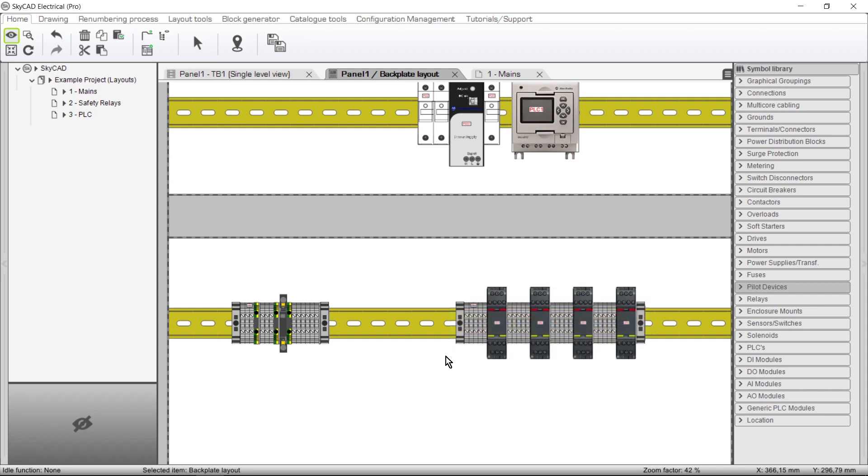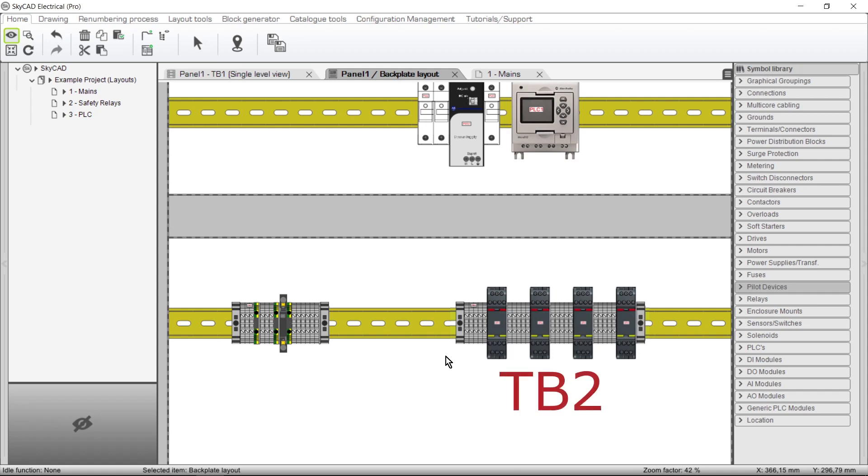which consists of some terminals, a safety relay, some more terminals, and so on. Conventionally, to achieve this layout, each set of terminals would have to belong to its own Terminal Strip, which may not be what you want, and it would be time consuming. Instead, have all these terminals belong to the same Terminal Strip, and add the safety relays to the Terminal Strip.